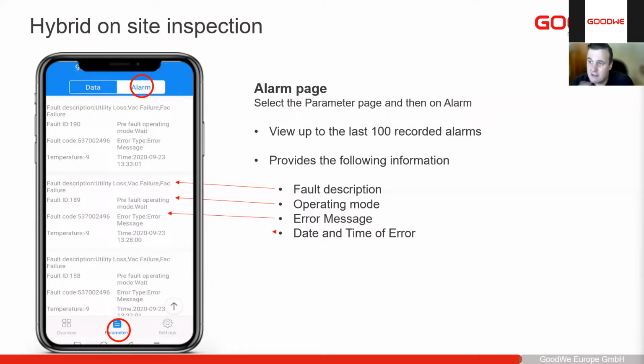So utility loss, it's a hybrid inverter. We have batteries, we have solar. Sometimes we might see wait mode in the middle of the night. The batteries are flat, there's no PV anymore, the grid is off, so now the device is idle and sitting in wait mode.